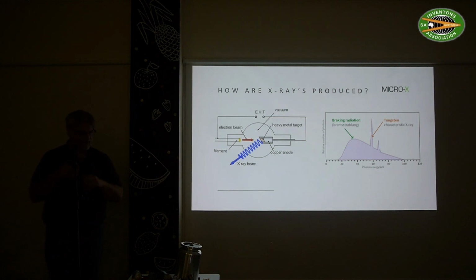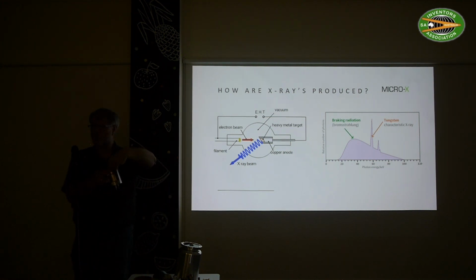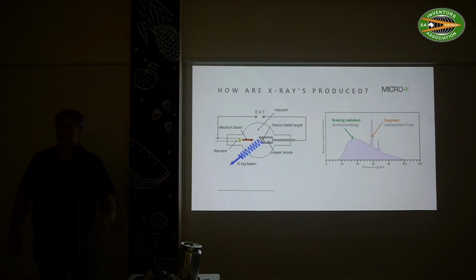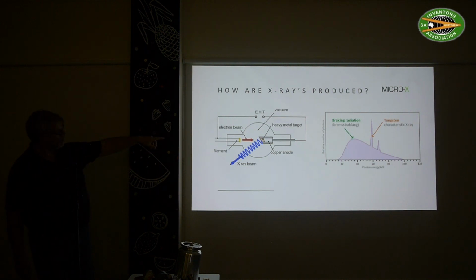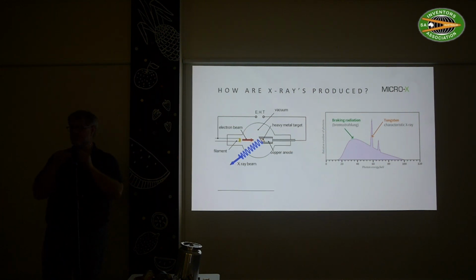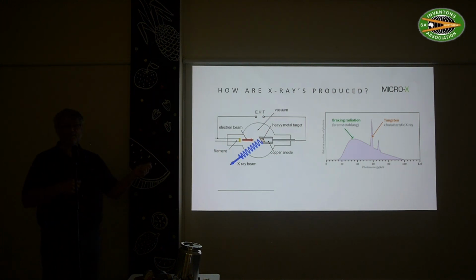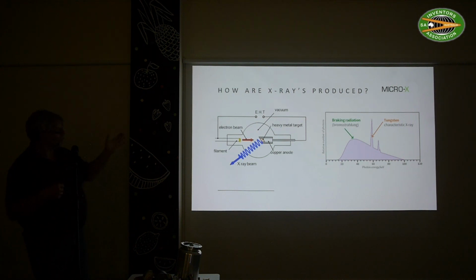And that typically is a very copper thing. I actually have some samples, like here. There's a big copper block in here. That is just to handle the heat that's going on, because on top of that anode, there's a little sliver of very dense metal, like tungsten. And what happens is that the electrons bump into the tungsten, and that is where the X-ray is produced. The interesting thing is that X-ray is only about 1% of the amount of electrons that bump into it. So the rest all disappears in heat. And when you're talking about 160,000 volts and you do 7.5 milliamps, you're talking about a kilowatt. So that is all interesting stuff that you need to manage. So that is the pure principle of how X-ray tubes work.